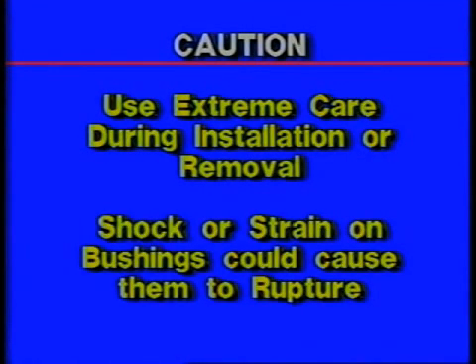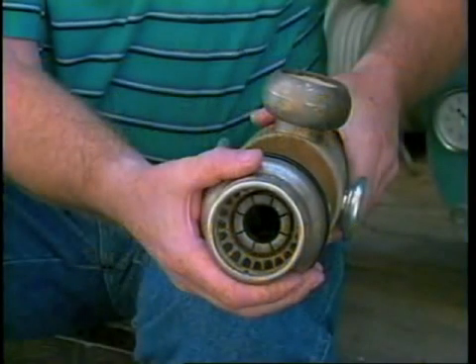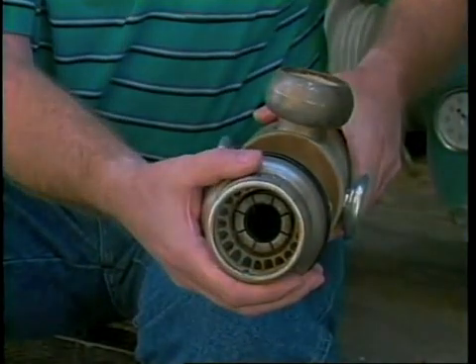Caution: if the bushings contain sulfur hexafluoride gas, extreme care must be exercised during installation or removal. Any shock or strain on the bushings could cause them to rupture.